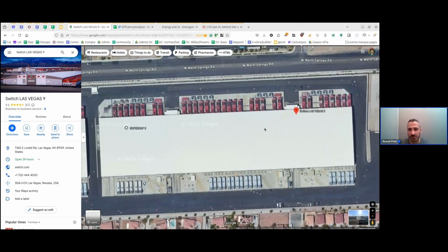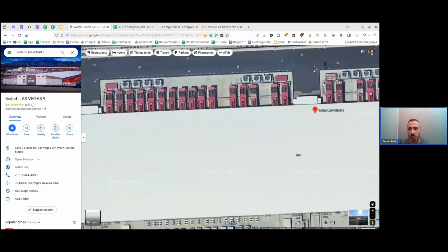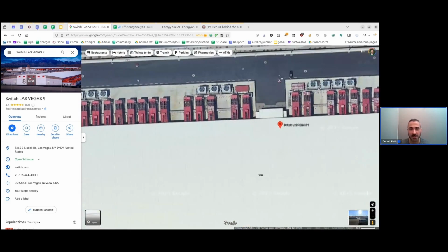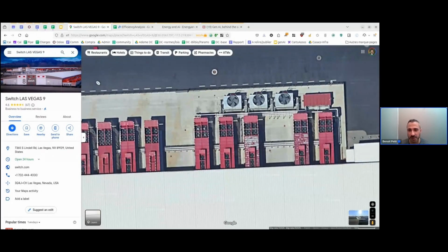Another interesting item is that it might look like a typical air cooling data center because we see fans, but actually those are not typical air cooling fans - they're water evaporation items, fans that expel vapor into the air. It's very different from the cooling towers we've seen before, which are very obvious and make a lot of vapor in the air - good for photographs if you want a nice picture for a newspaper article. These items here are much more discreet, much more hidden, and also much smaller.